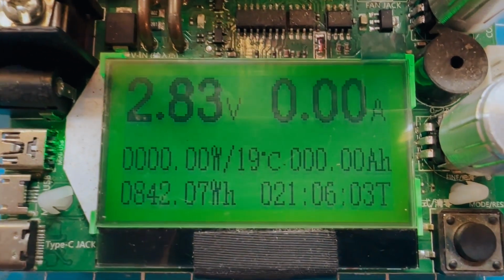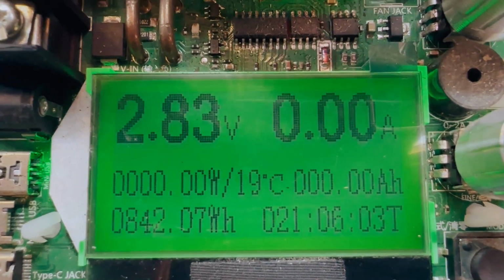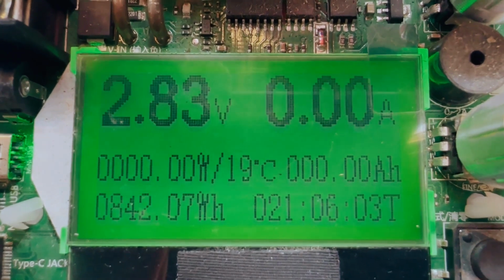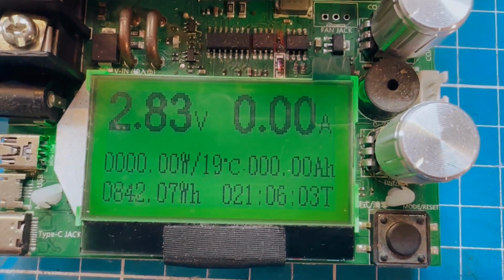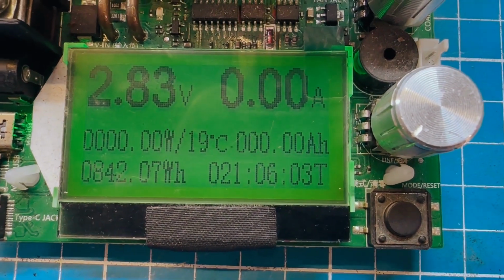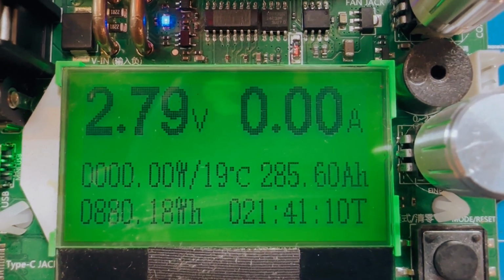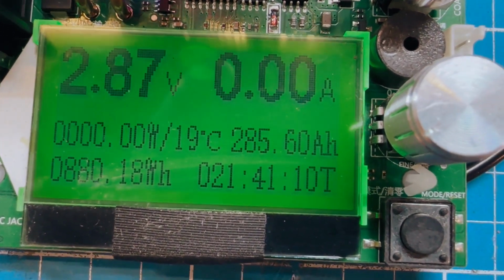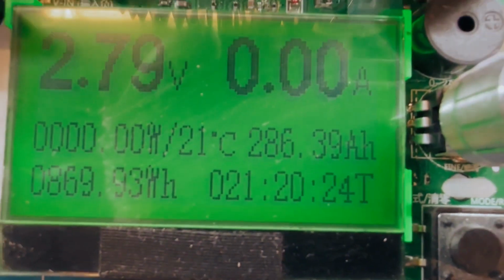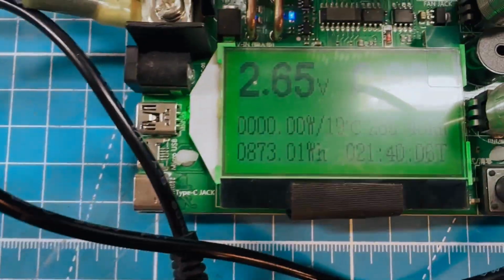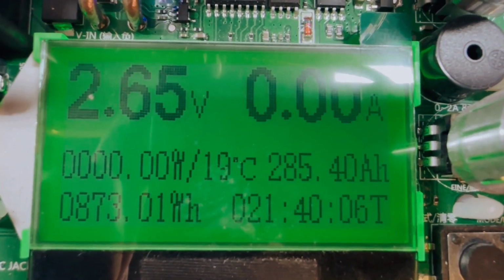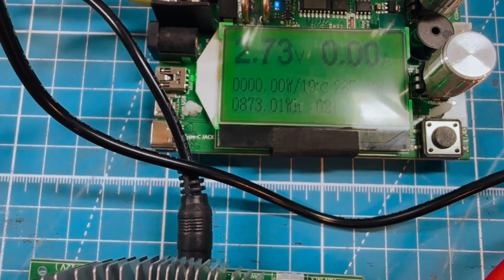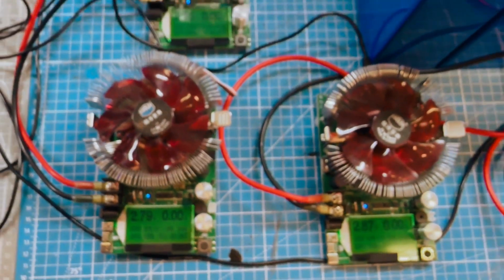Right, so the capacity test is completed. This one I reset by mistake, but it would have been about 287, 288 amp hours, so well within capacity. It's bounced back to its resting voltage of 2.83. This one has gone 285.6 and back at its resting voltage, 286.3, and 285.4. All of them 2.6 to 2.8. So every single cell has met capacity.